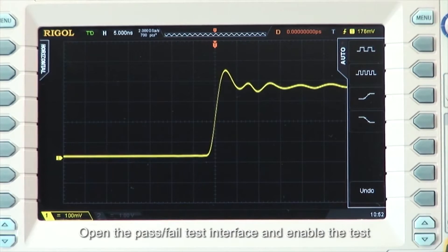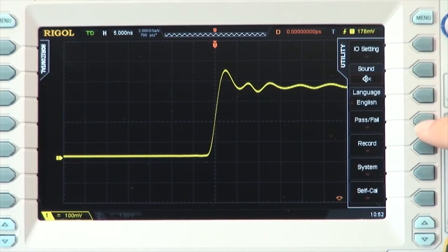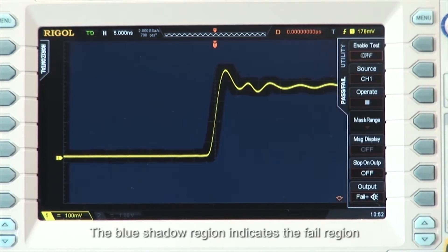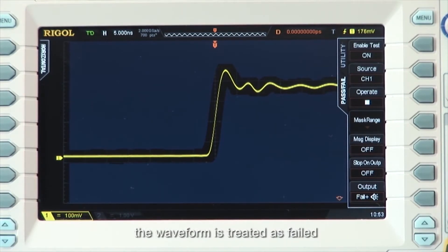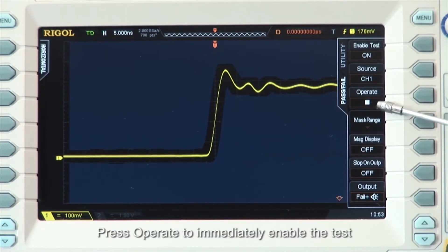Open the pass-fail test interface and enable the test. The blue shadow region indicates the failed region. During the test, if the waveform measured at a certain time passes through the fail region, the waveform is treated as a failure. Press Operate to immediately enable the test.